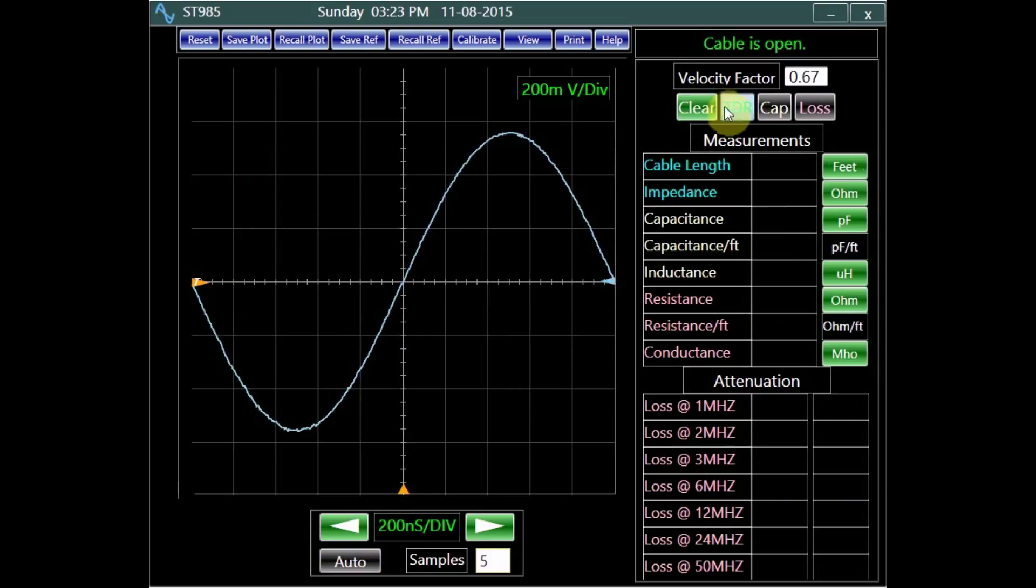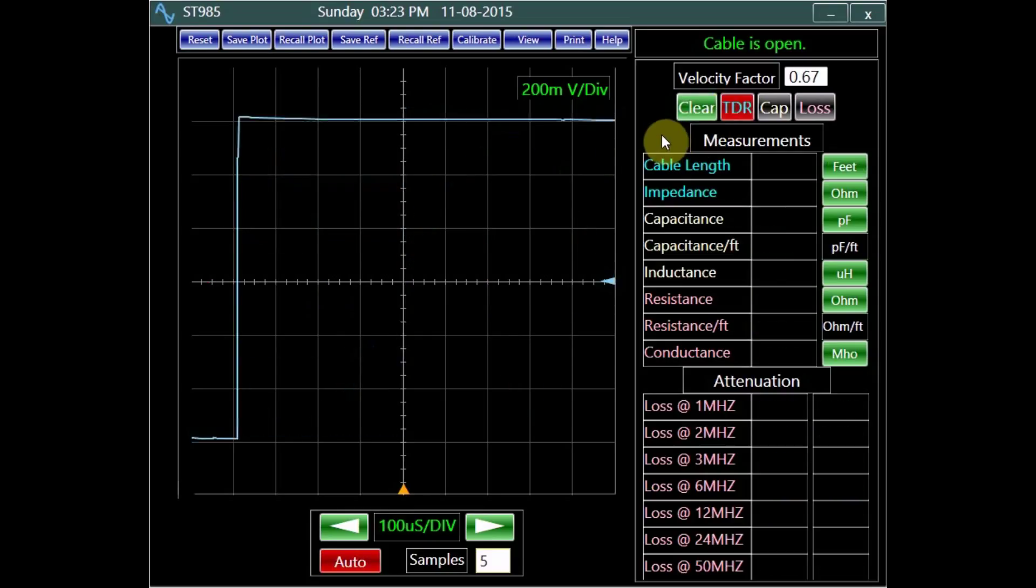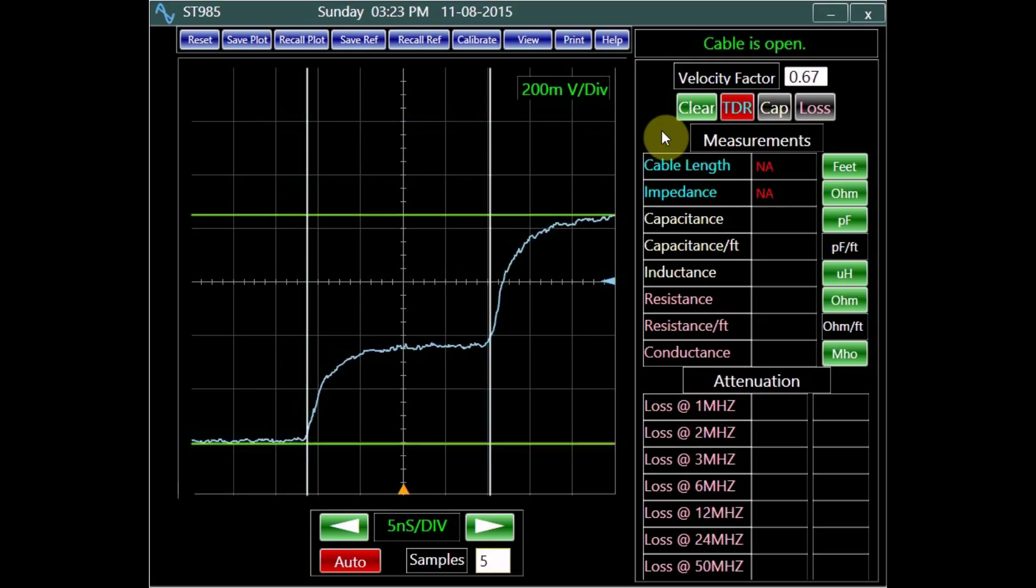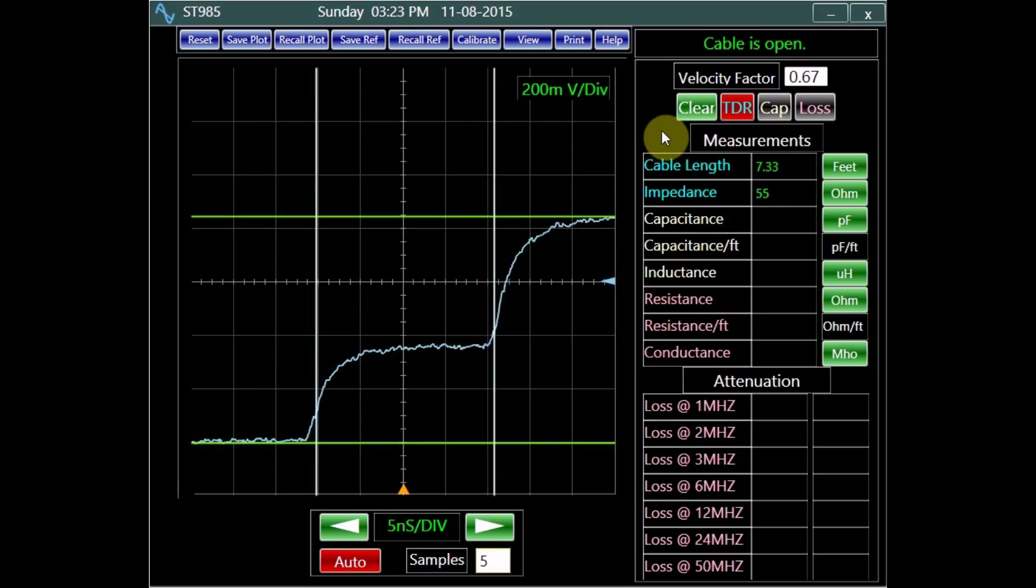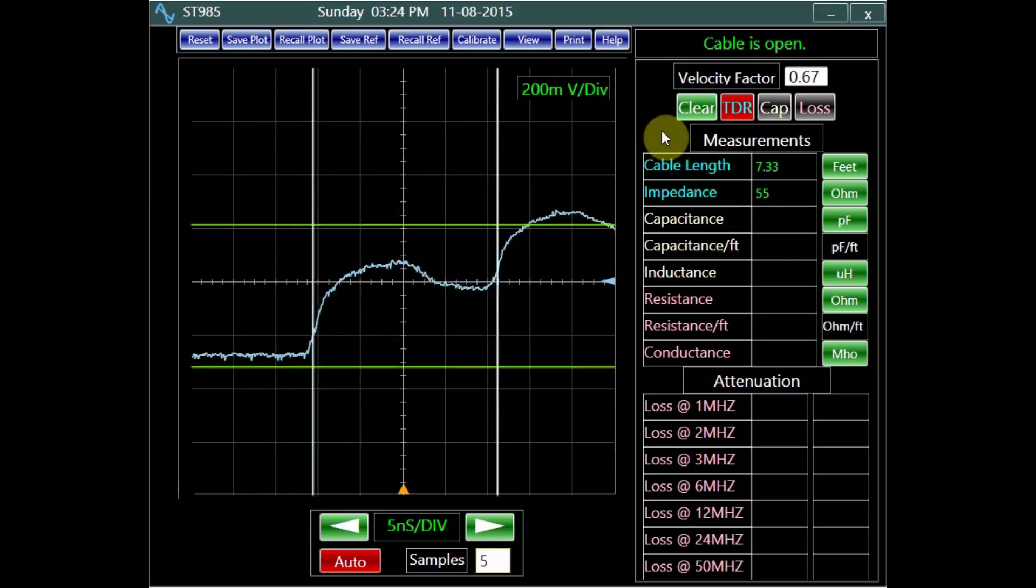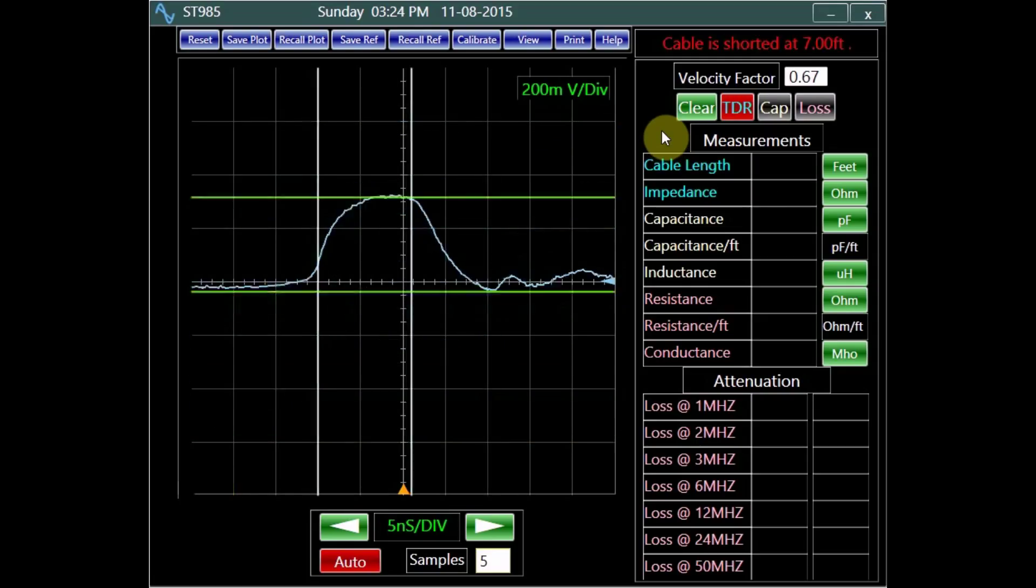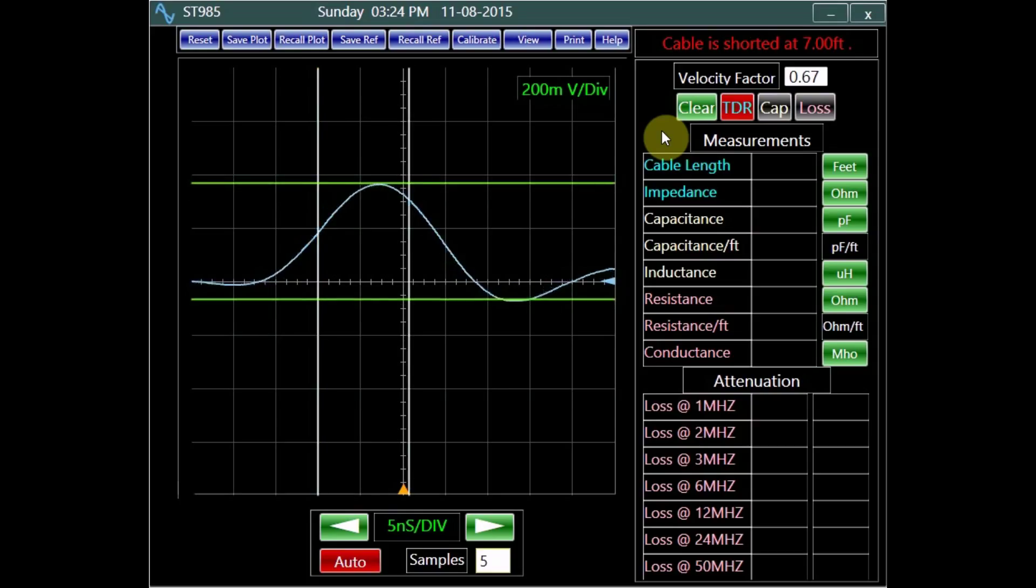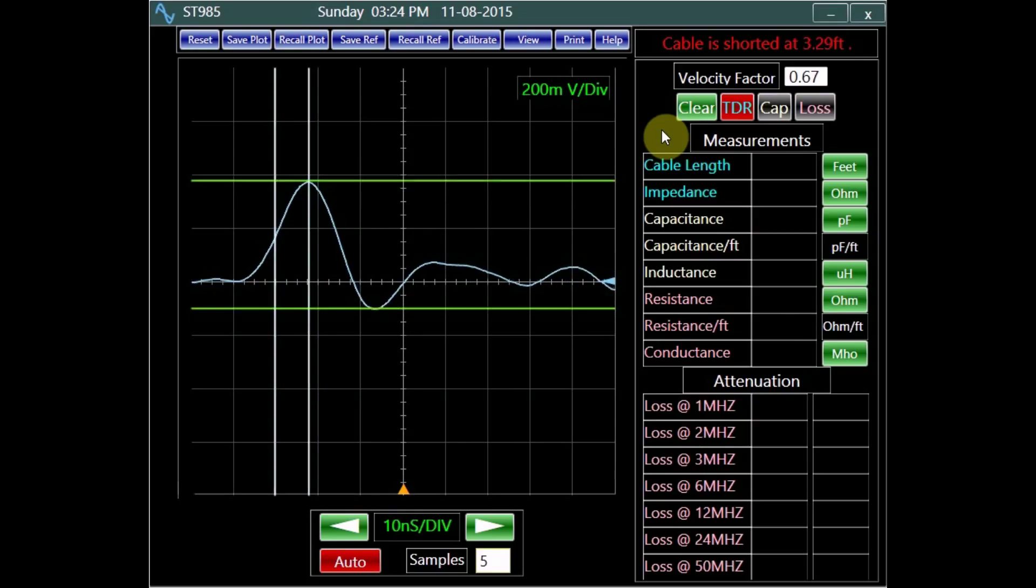In the TDR mode, channel 2 automatically measures cable's length and impedance. It also finds the location of shorts, opens, and most other faults.